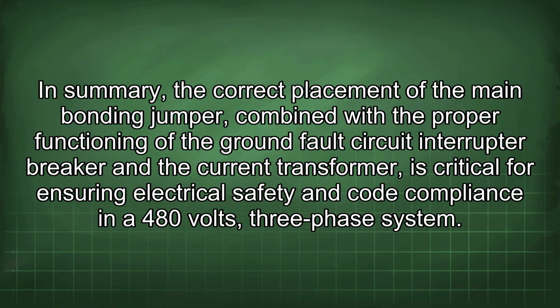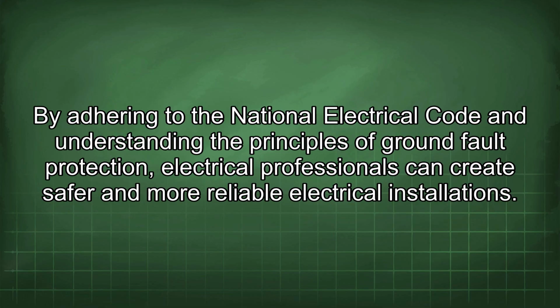In summary, the correct placement of the main bonding jumper combined with the proper functioning of the ground fault circuit interrupter breaker and the current transformer is critical for ensuring electrical safety and code compliance in a 480 volts three-phase system. By adhering to the National Electrical Code and understanding the principles of ground fault protection, electrical professionals can create safer and more reliable electrical installations.